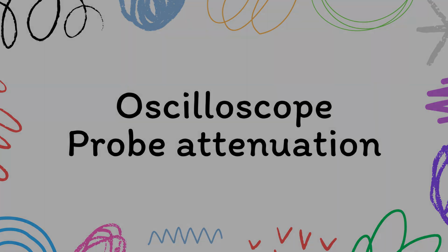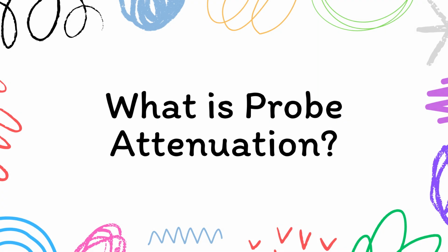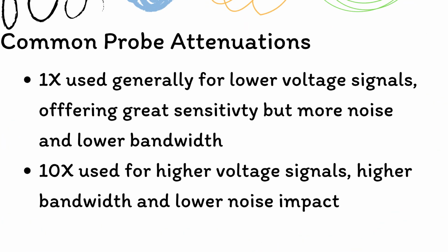What is probe attenuation? Probe attenuation is a feature that reduces a signal's voltage before it reaches the oscilloscope input. By lowering the voltage level, the scope can safely measure signals that might otherwise exceed its input range, preventing the distortion of the signal or even damage to the instrument. Common attenuation types include 1x, 10x, and 100x settings. For example, a 10x setting reduces the signal by a factor of 10, meaning if the real signal is 10 volts, the oscilloscope only receives 1 volt.